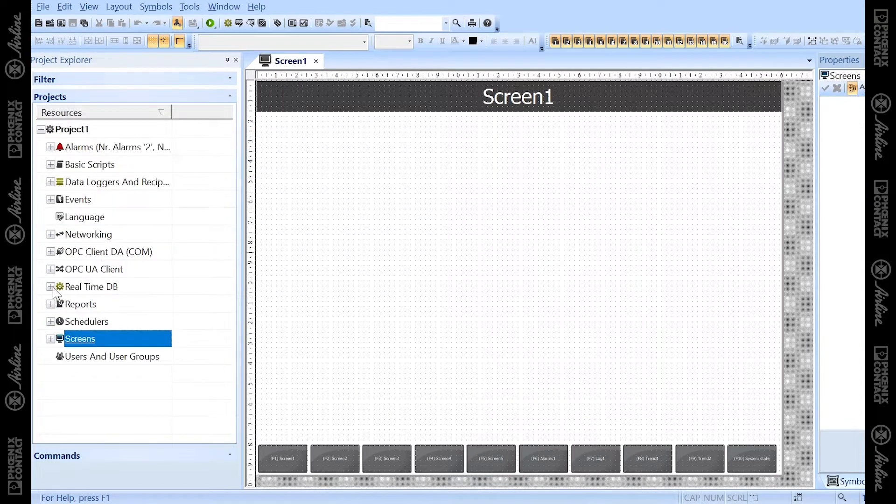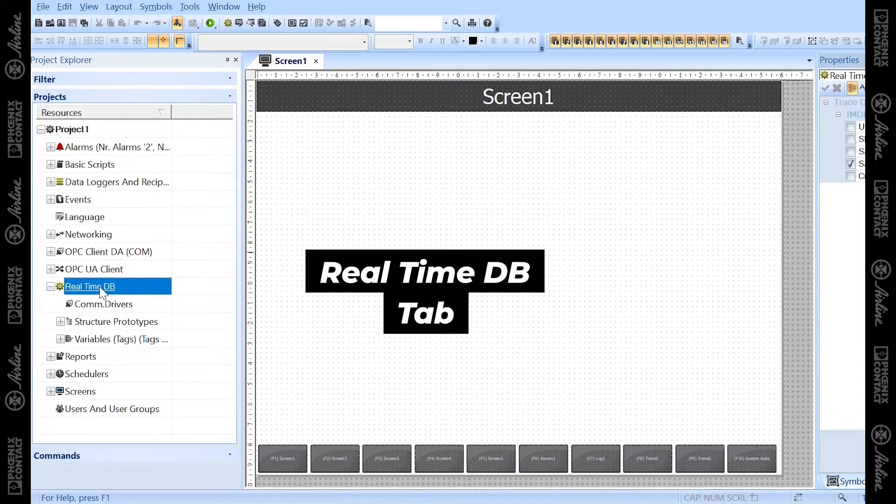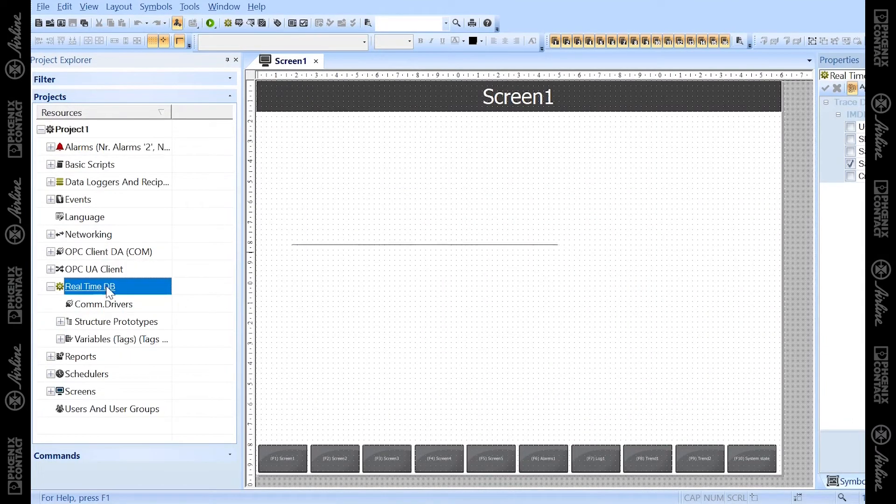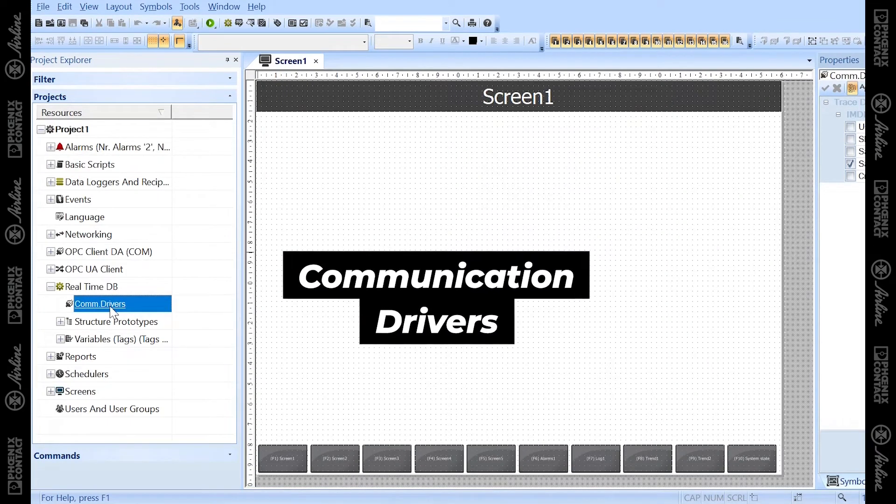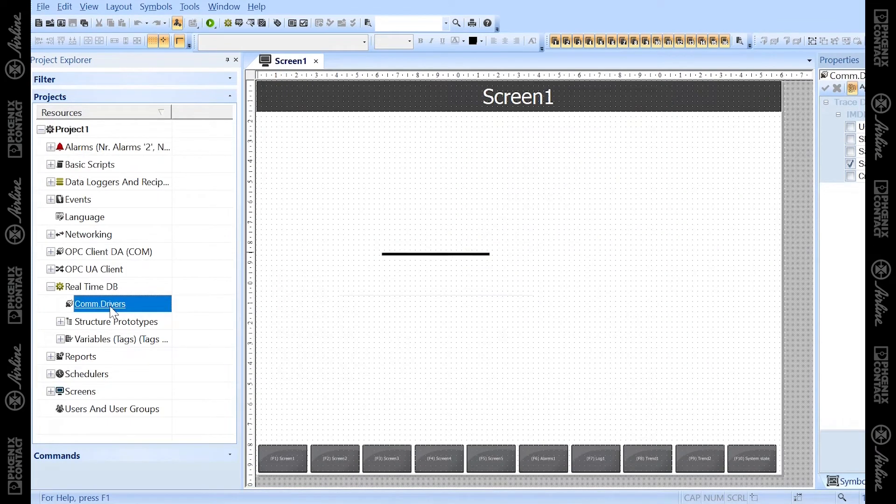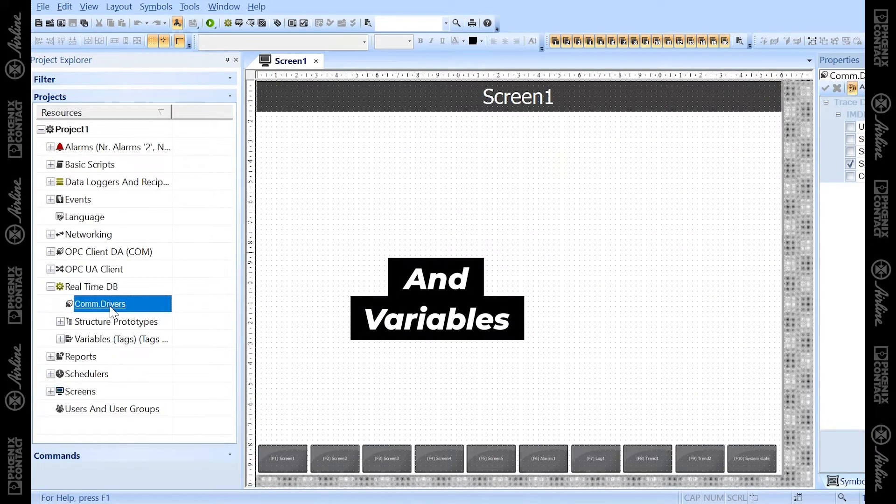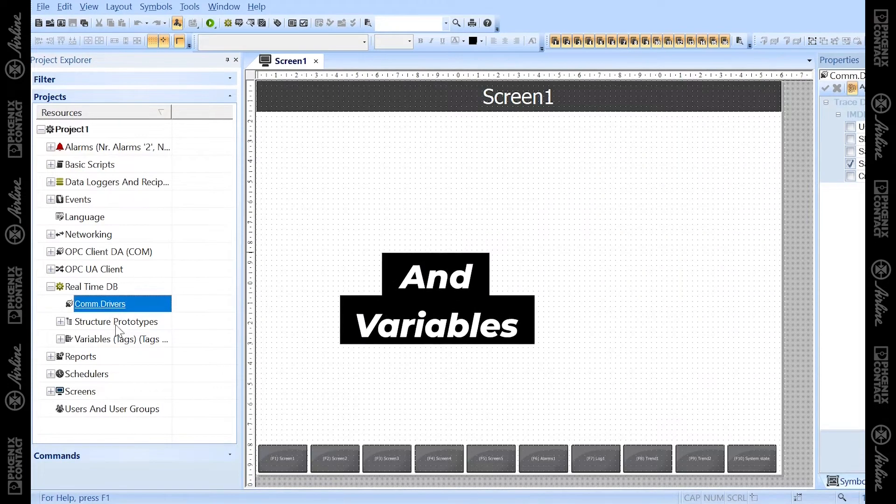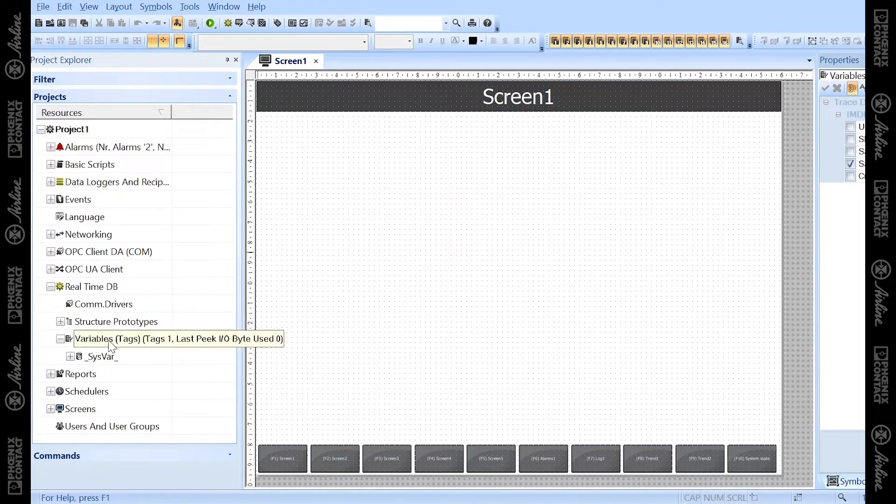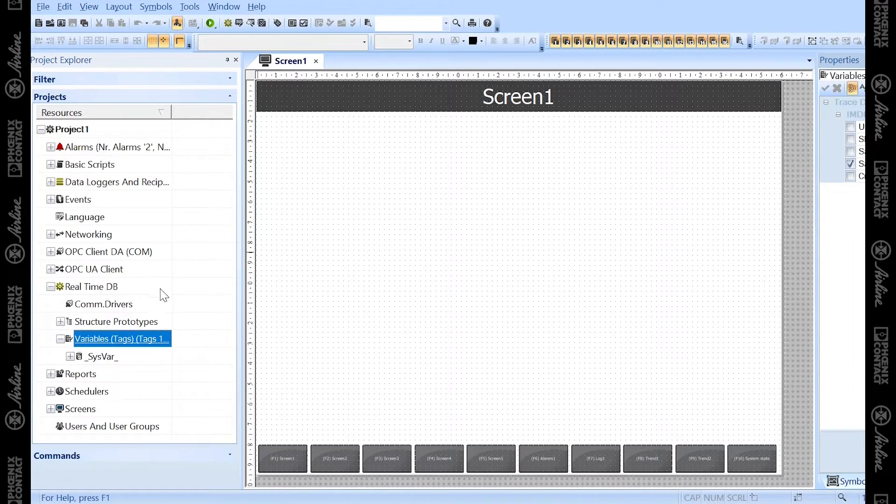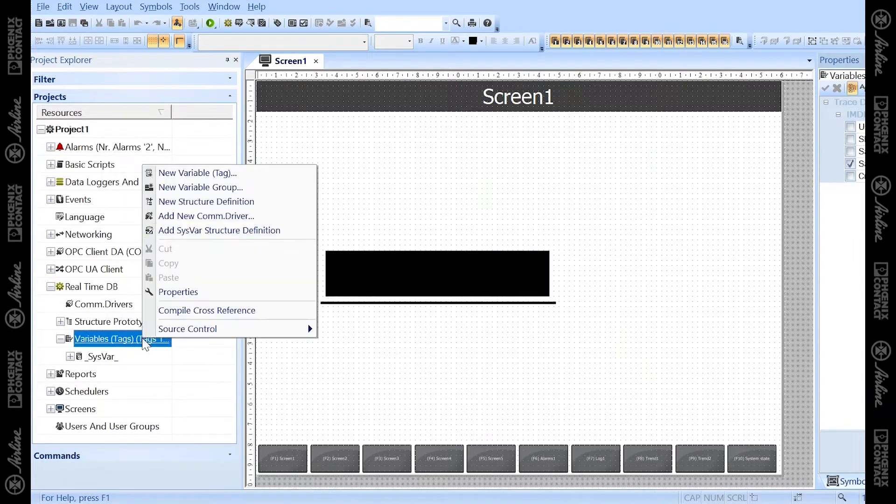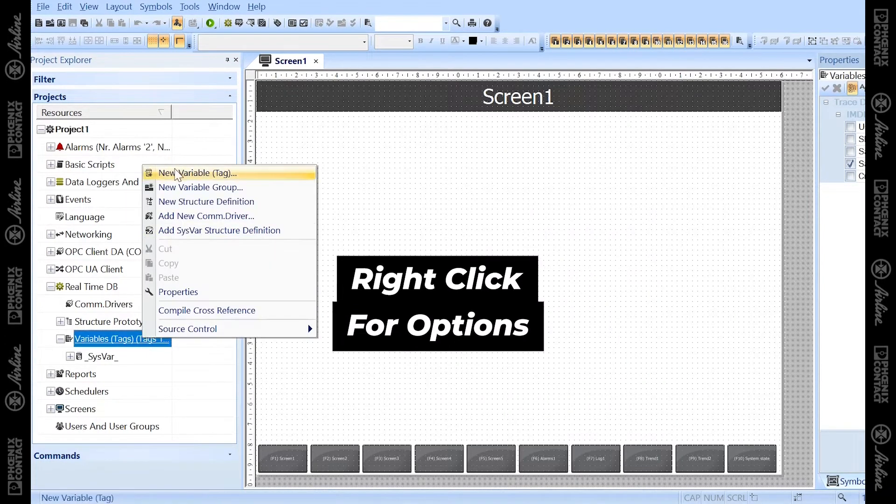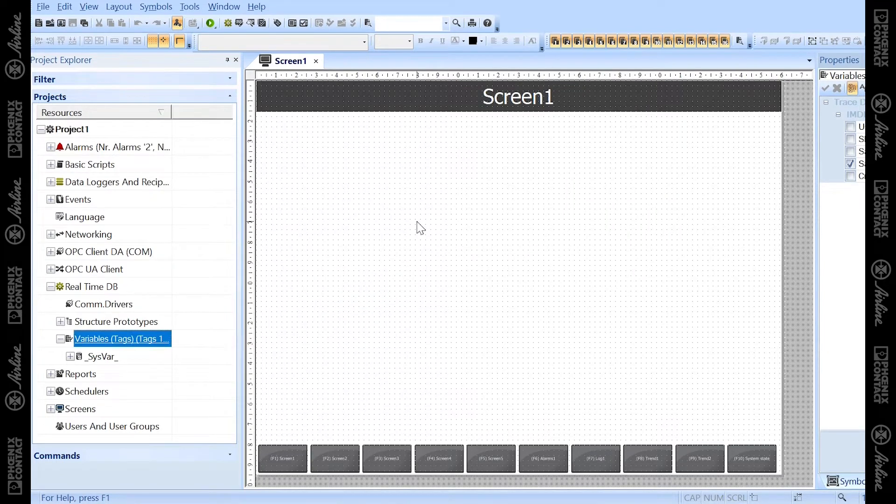The second thing I want to cover is the Realtime DB tab. Under this is where you'll find your communication drivers to connect to your PLC and pull in your variables. Once those variables are pulled in, they'll show up under this Variables tab here, which is still under Realtime DB. You can use those variables or add a local variable here to link them to your objects to make different things happen on your HMI screens.